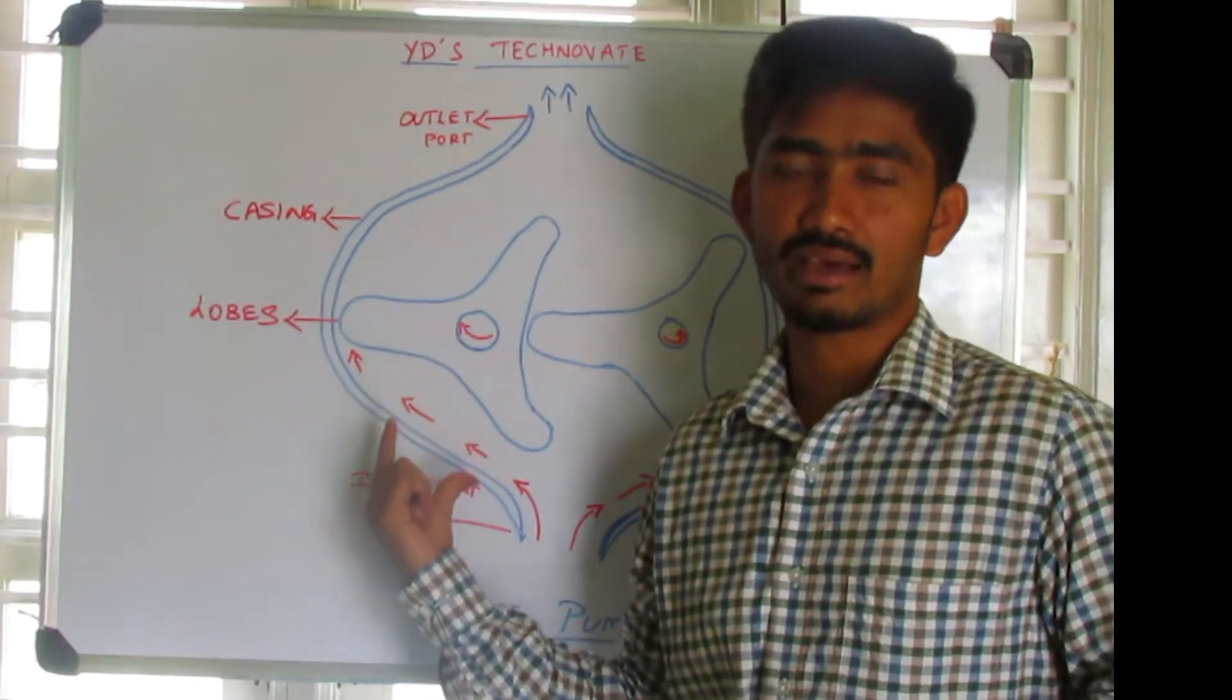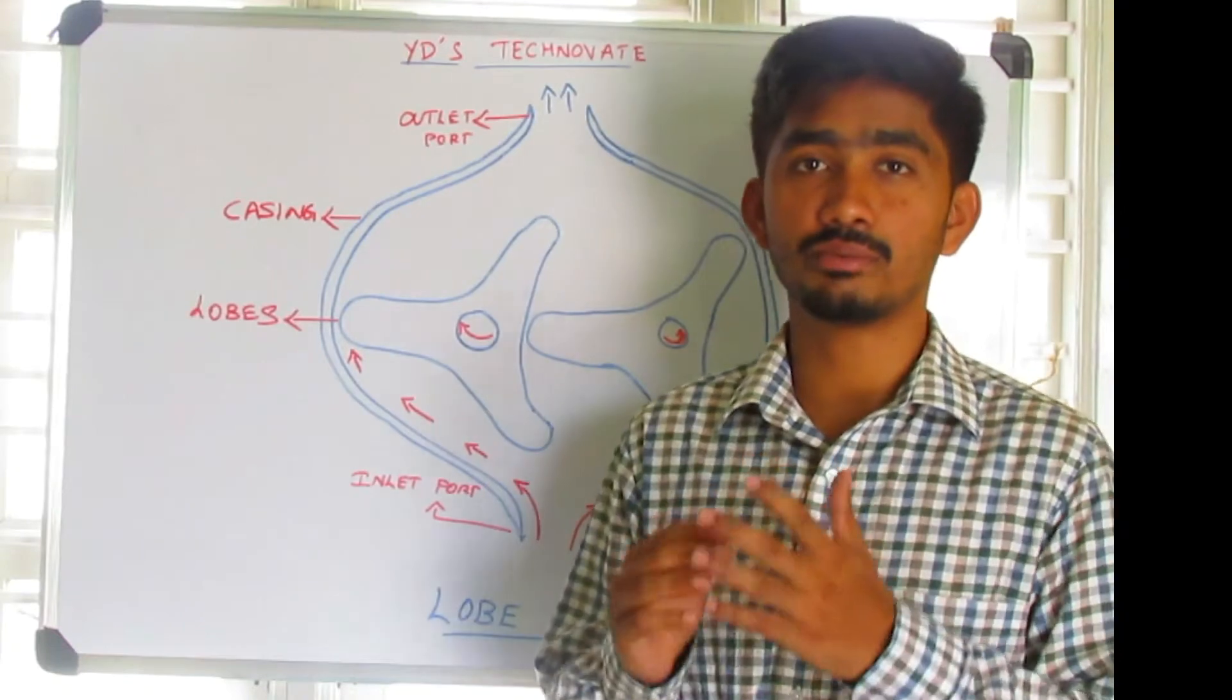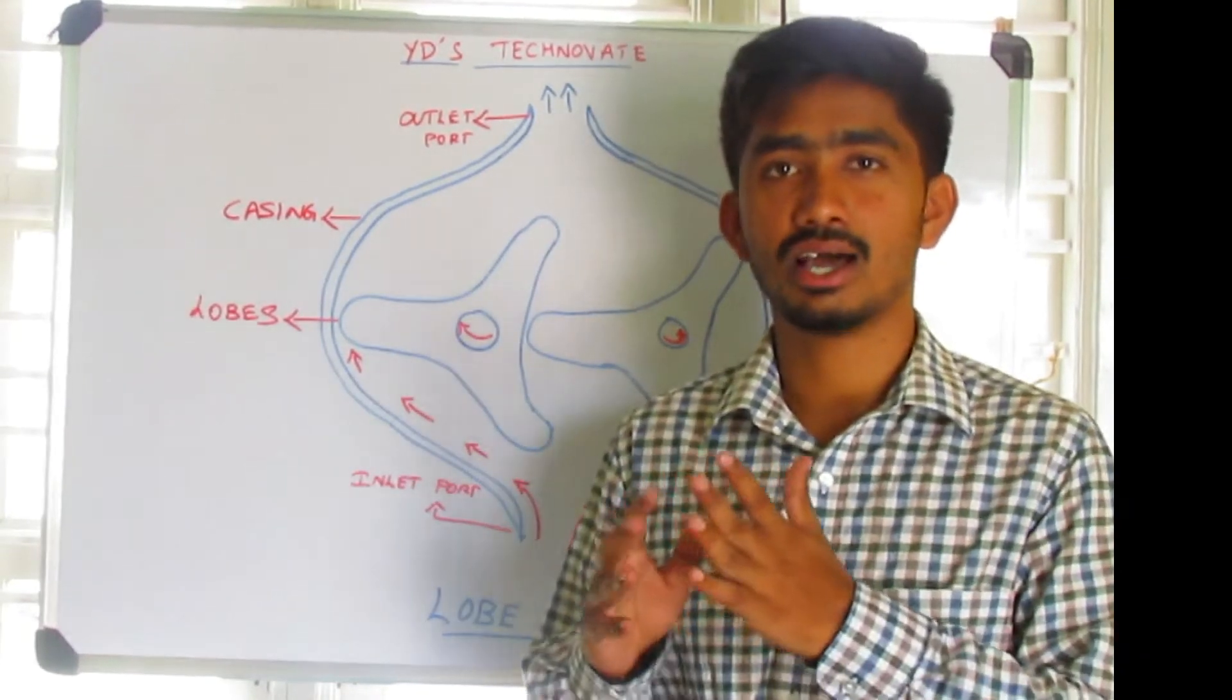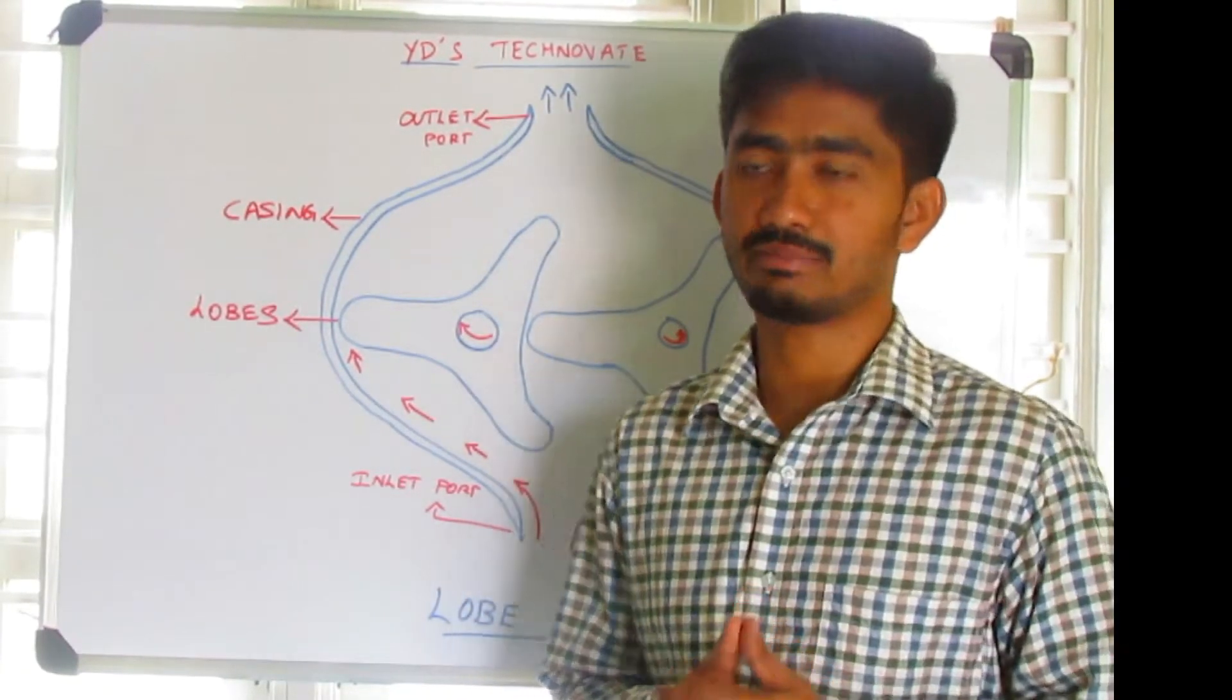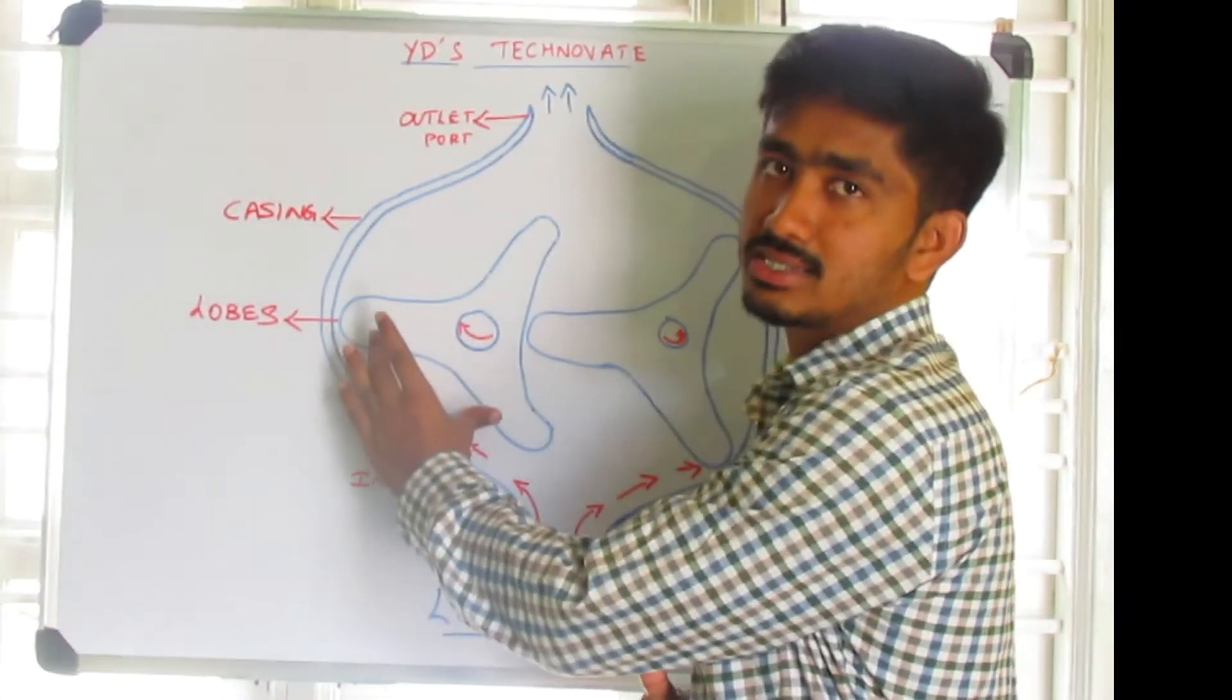So this causes pulsations in the flow and also the volumetric displacement will be high when compared to external gear pumps. As we can see, the gap between these two teeth is very much high, hence the volumetric displacement will also be high when it is compared with external gear pumps.